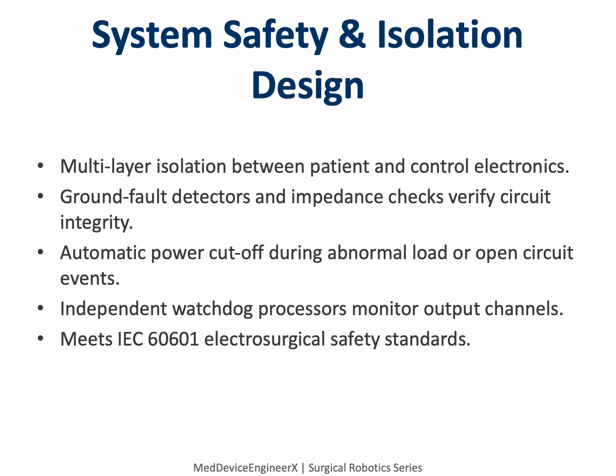Safety within the Hugo's energy system is built like concentric shields, each layer catching what the previous one might miss. Isolation barriers separate the generator's high voltage sections from the patient interface and from the robot's digital controllers. Before activation, the tower performs impedance and return electrode checks to confirm a secure circuit. If an open circuit, a ground fault, or abnormal impedance is detected, the watchdog processors cut power instantly and alert the console. Redundant microcontrollers cross-check each other's readings, eliminating single point failure risk.